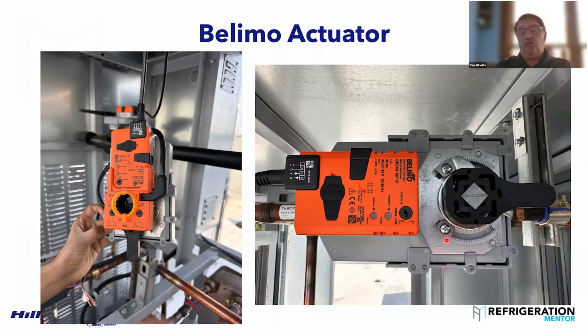That's correct. So one of the ones that I usually set is the bottom end. Say you're in a state where in the summertime it's so dry, the heat reclaim is not going to work. Let's say Arizona. It's dry, the store needs humidification, not dehumidification. So this valve is going to stay closed for 70% of the year. I want vapor moving through that coil, so I'll set that for 10%. That way we're always moving vapor through the coil. We're not allowing the AC condenser to condense 50, 60 pounds of liquid over on that side of the system, and we're not trapping oil over there.